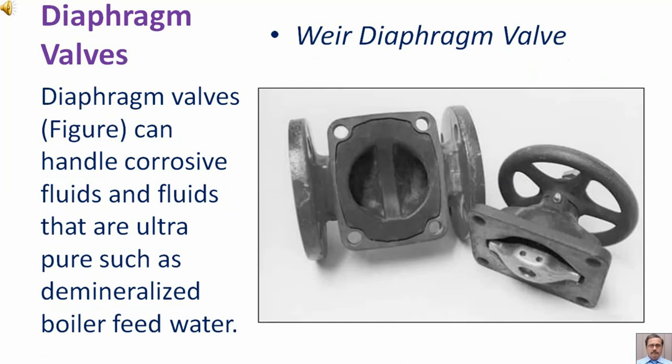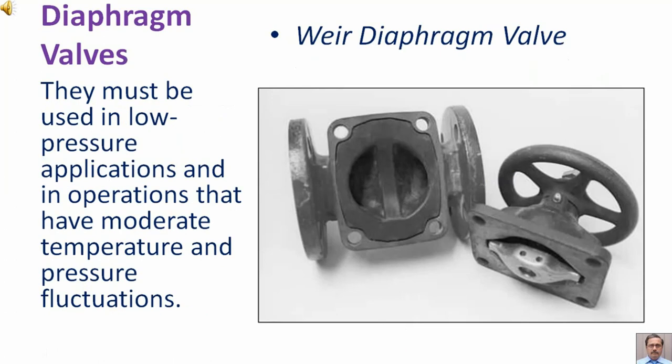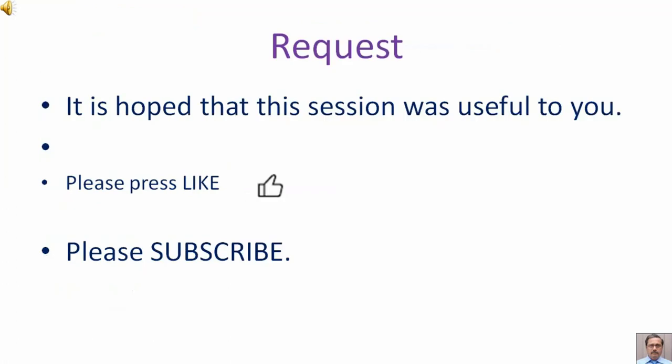Diaphragm valves can handle corrosive fluids and fluids that are ultra-pure, such as demineralized boiler feed water. They must be used in low-pressure applications and in operations that have moderate temperature and pressure fluctuations.